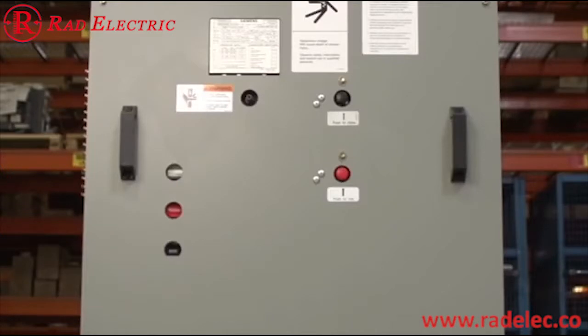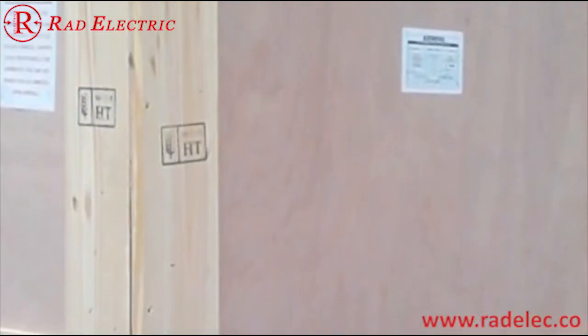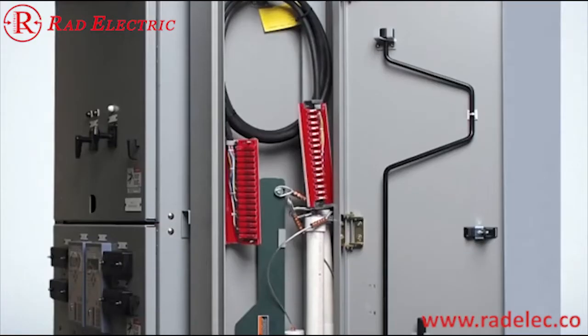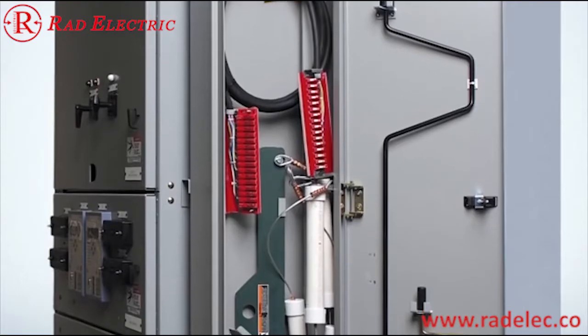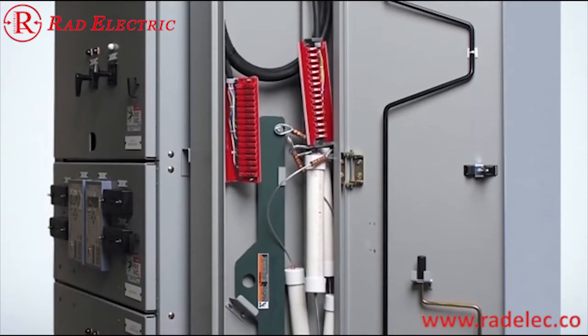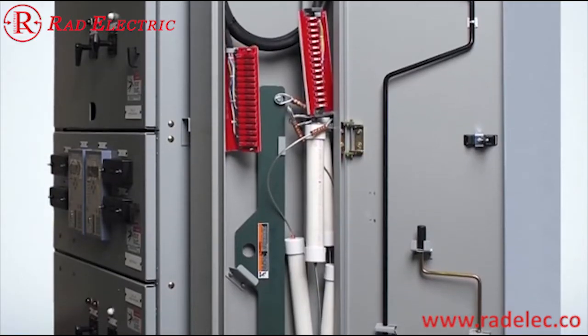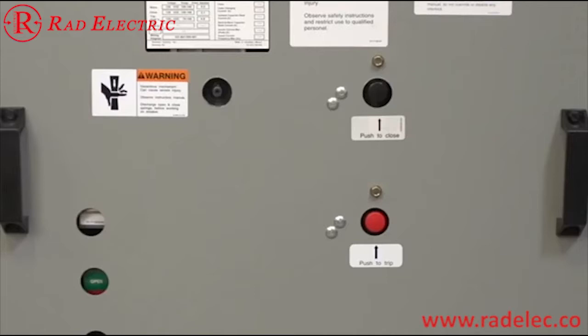Next, let's discuss the most important element of the switchgear, the vacuum circuit breaker. When you receive your GMSG vacuum circuit breaker, always inspect the shipping container before removing or unpacking the unit. Check for shipping damage or rough handling by the carrier. Also, check each item against the packing list to identify any shortages. Accessories like the manual charging crank, the racking crank, and the split plug jumper ship separately. After you unpack the circuit breaker, please observe that it is normally shipped with primary contacts open and springs discharged. It's important to verify the discharged condition of the spring-loaded mechanism after de-energizing control power. We'll demonstrate this later in this video.